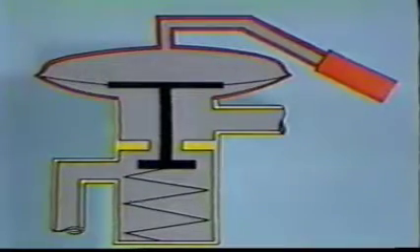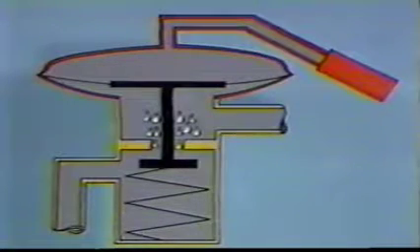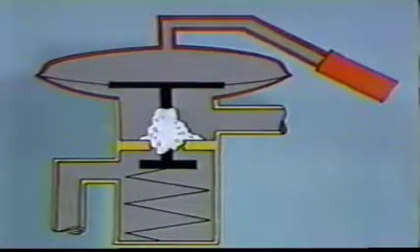The operating port of the expansion valve can be the smallest orifice in the system. It takes very little contamination to cause it to clog and shut off flow to the evaporator. Any contaminant is harmful to an expansion valve, but the one that is least obvious but that can cause the most trouble is water. Any moisture that is dissolved in the refrigerant will condense out as the refrigerant drops in both pressure and temperature at the valve orifice. As the resulting ice crystals collect at the orifice, flow will be reduced.